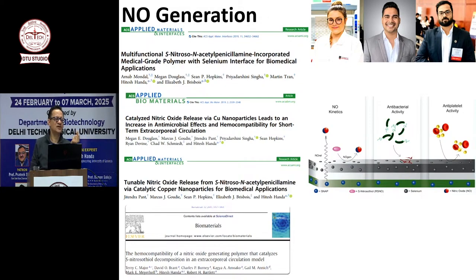So for catheters, if you want a catheter to be 2 millimeter outer diameter, we can have an inner diameter of, let's say, 1 millimeter, and outer diameter of 2 millimeters, so that is our working thickness, right? Here, if we have a coating of a tubing, we can make a 100 micron thick coating. It just depends on the application, how much room you have for a thick or thin coating. But yes, the thinner the coating, the less SNAP you can put in.